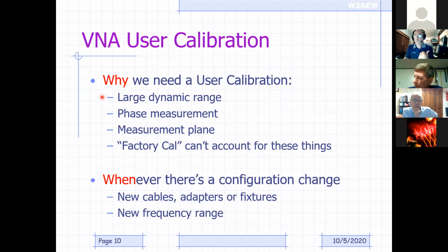Okay. And when we do a calibration is whenever there's a configuration change, meaning I've got a different set of cables, or I've changed the adapters, or I've changed the fixture, or most commonly, when you define a new measurement frequency range that you want to measure. That's when you do a quick user cal. And it's a simple thing to do. The menus walk you right through it. But if you pick up your MFJ 259, well, I don't have to calibrate this. Why do I have to calibrate the NanoVNA? Well, these are the reasons why. Okay.